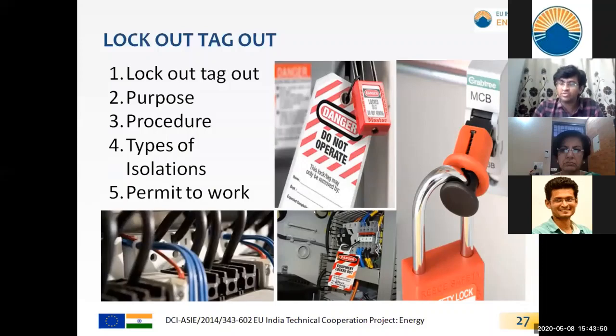For example, if two or more persons are working on the same line, then each person has to put a lock on the same switch. We have devices for that, like the hasp lock, where we can lock up to 8 persons. Until all 8 persons remove their locks from the hasp lock, it will not be removed from that particular switch. This safety device comes in handy when doing isolation, to prevent unauthorized energization of that particular line.